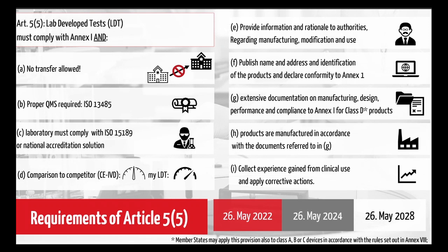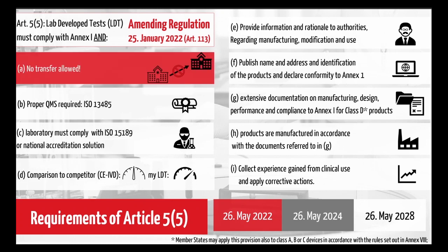First of all, these lab-developed tests, or we should better call them in-house IVD devices, must comply with Annex 1, which means the general safety and performance requirements of the IVDR. That is already a long list of requirements to be fulfilled. And in addition, it is not allowed to transfer these devices. This is to be applied with the amending regulation from 25th of January 2022, already since 26th of May 2022. You see it in red down at the bottom right side.